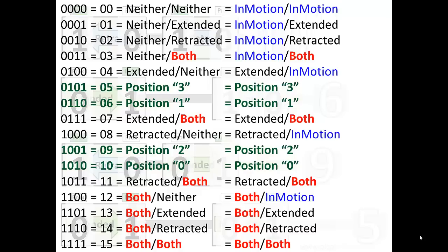So what would you add to an in motion state to determine if it was a problem or not? In other words, let's say the cylinder did extend or retract and neither sensor is made. It left one that was made and never made the one at the other end, either because the cable's been stepped on by an operator climbing on the machine and he pulled the cable out and broke the conductor or the machine is jammed, you name it. Well, you simply add a matter of time. So anytime you have an in motion state, if you add a timer, if the timer times out, then you have a fault. So this is just a little sidetrack here to give you some ideas for other applications. It really has nothing to do with the add-on instruction, but I thought I would throw it in there free.